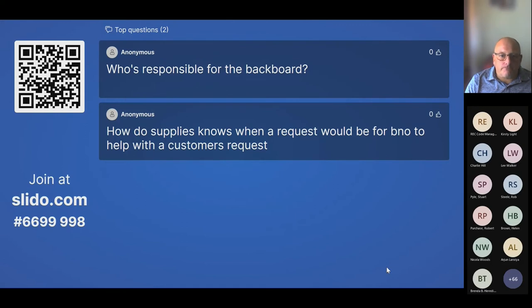If you have trained smart meter engineers, they can fit isolators, but not if they're not working for a specific supplier. That's the change going through at the moment. The ruling under the MCOP says you're only allowed to work on behalf of the supplier. So if you're working for the supplier and you're the responsible MEM, and they've asked you to fit one, that's not an issue. What you can't do is fit one where you're not the appointed MEM via the supplier. That's the change going through MCOP currently.